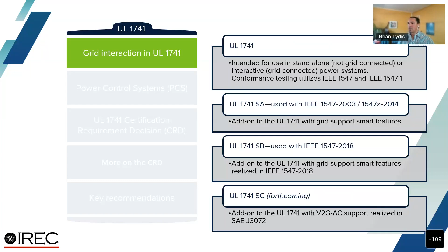And there's strong familiarity, therefore, with 1741 amongst the utilities and utility engineers over many years now, allowing certification of inverters to be trusted as the main means of verification of compliance with 1547. So it makes it fairly easy if you've got a certified inverter being the interface to the grid. The utility, at least in the past, hasn't needed to check much else about the system to determine that you are in compliance with 1547, because the inverter itself ensures that compliance.